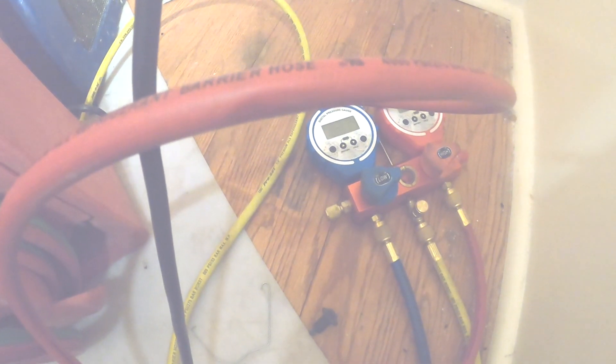I'm going to add a little refrigerant in it and see if I can get the pressures up. If the pressure goes up a little bit, I'll probably just have a leak. But if it stays in the negative even though I add a little refrigerant, I know I got a restriction.